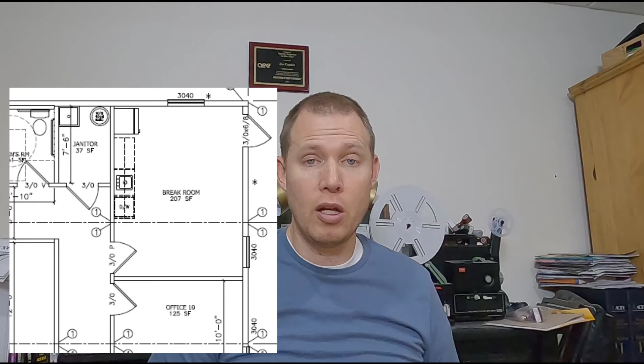Nobody's going to be in the break room for long enough to notice or to complain. And if the break room does fill up with people during lunch, it won't take long for it to revert back to the same temperature as all of the surrounding areas afterwards. It's just not a really critical area. The same could be said for the janitor's closet that's next to the break room. It has an entirely unique loading pattern, which is that there's almost no load in it ever. That's a good example of how a unique loading pattern does not qualify for an additional system or for a thermostat.